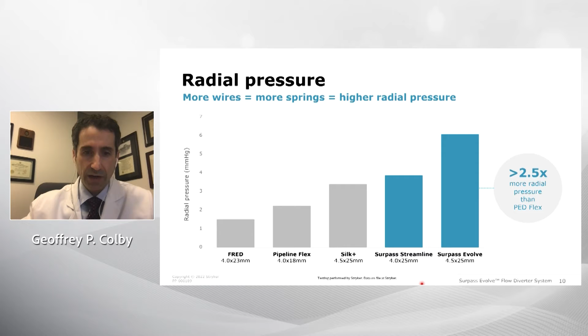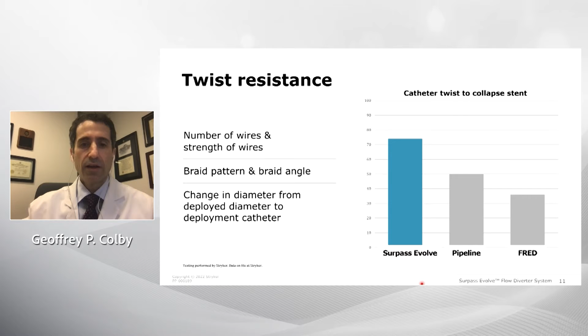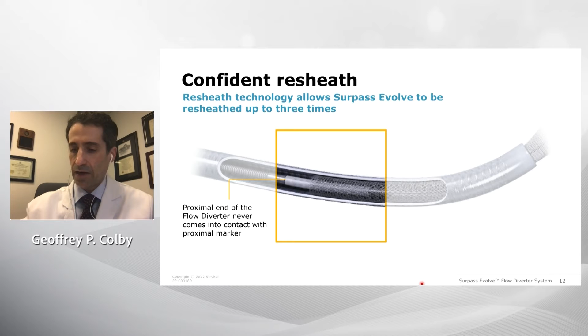Importantly, this device is also more twist resistant. This is one of the dreaded fears of doing a complex flow diversion case, that the device will twist and not open up. And Surpass Evolve is more resistant to that because of the braid angle and the 64 wires. It has a resheathing pad on the proximal end. This allows resheathing up to 3 times safely. In common practice, it can be done more than that, but the IFU states 3 times, and it works very nicely with very low friction forces.